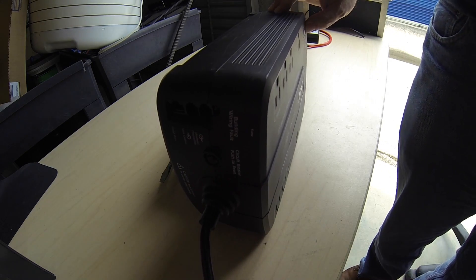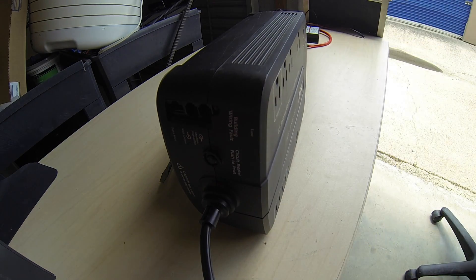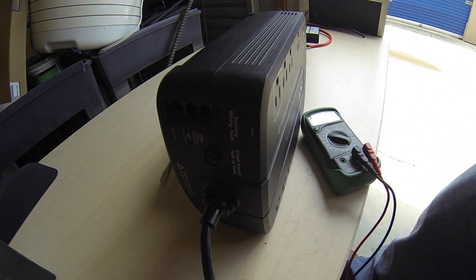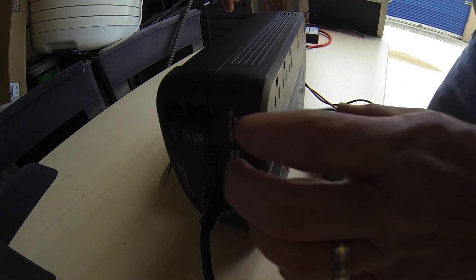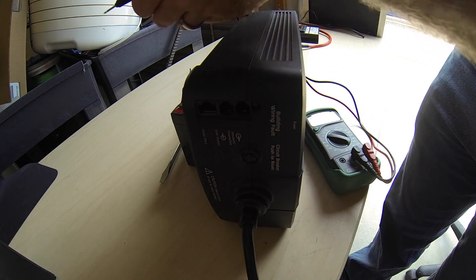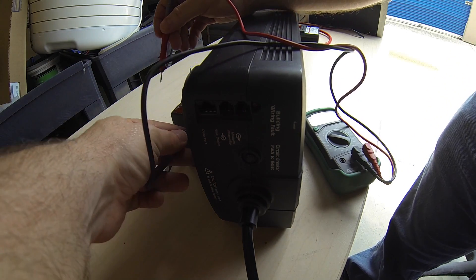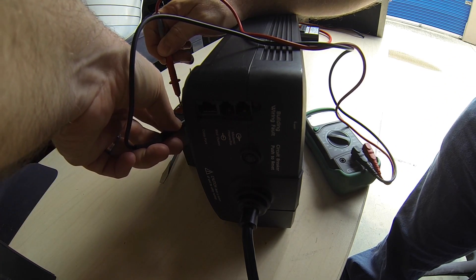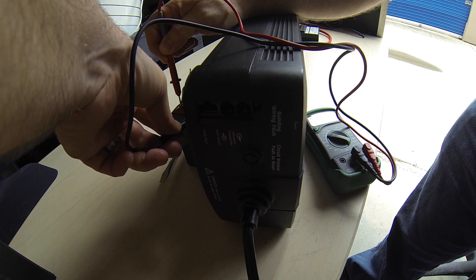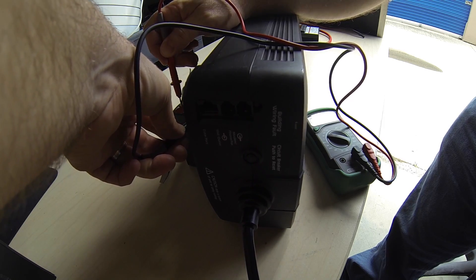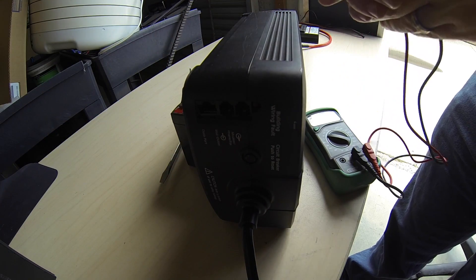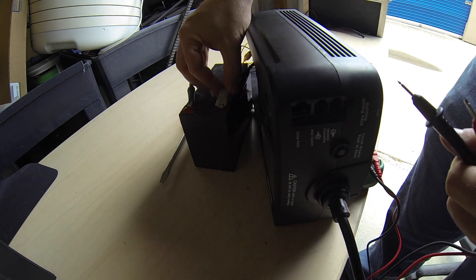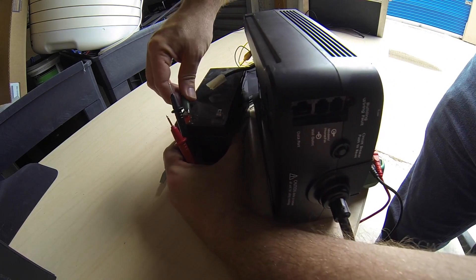APCs do require some voltage to turn on, to kick their relay over. This battery is dead. This is 9 volts. So, it's not going to work. Let's see if I can find a different battery that has more voltage in it than 9 volts.